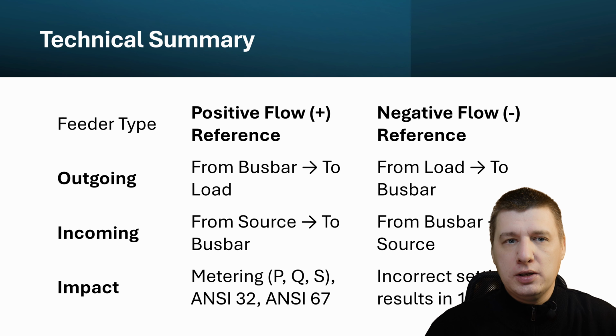Think of power direction like the direction of a turnstile at a stadium. If the turnstile is set to entrance, incoming, it counts positive every time someone enters the building. If it is set to outgoing, it counts positive every time someone leaves. If you accidentally set an exit turnstile to entrance mode, the computer will think people are entering the building and give you a negative count.